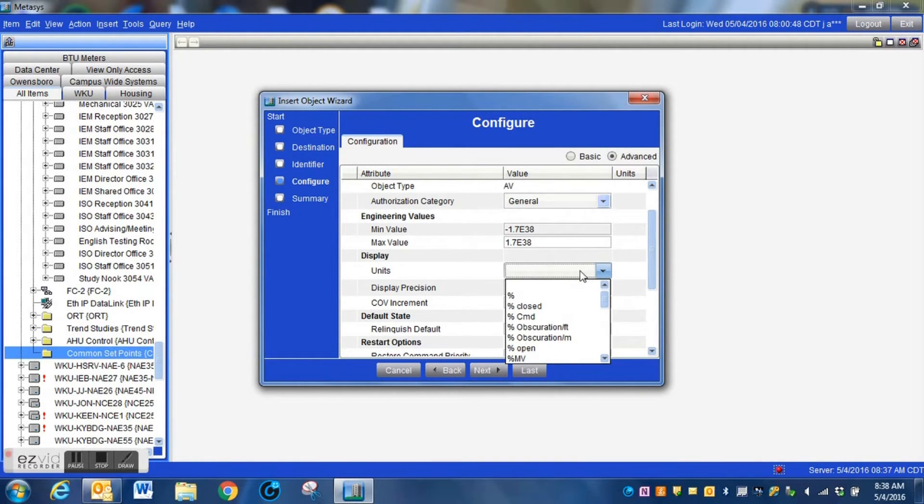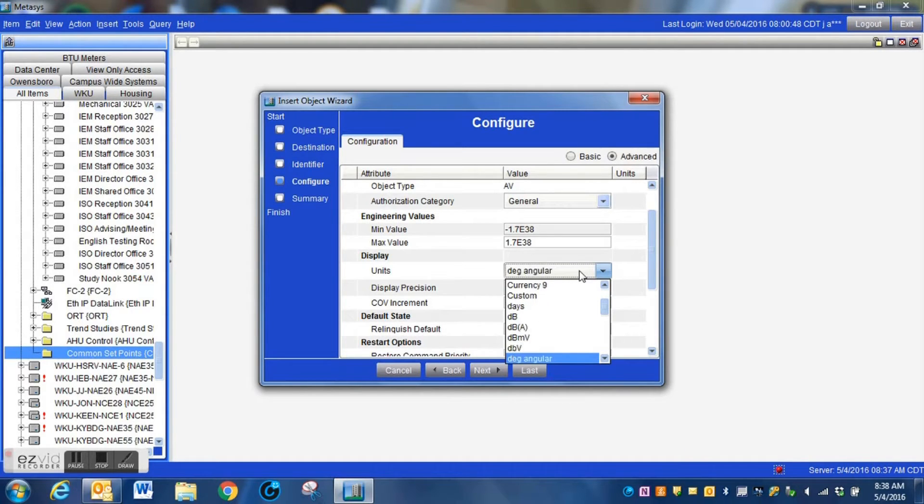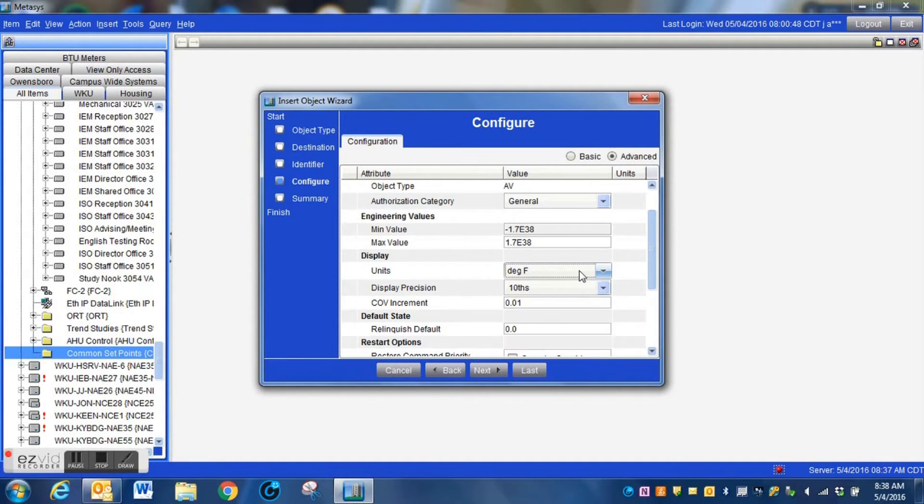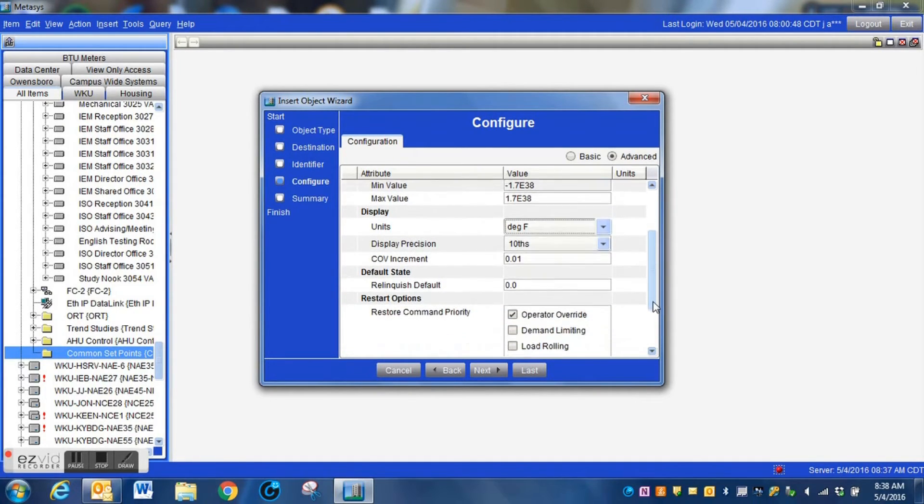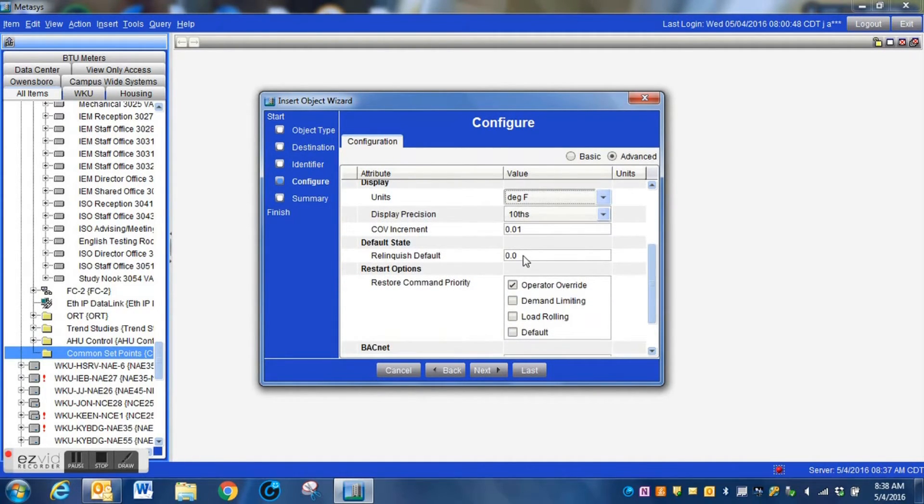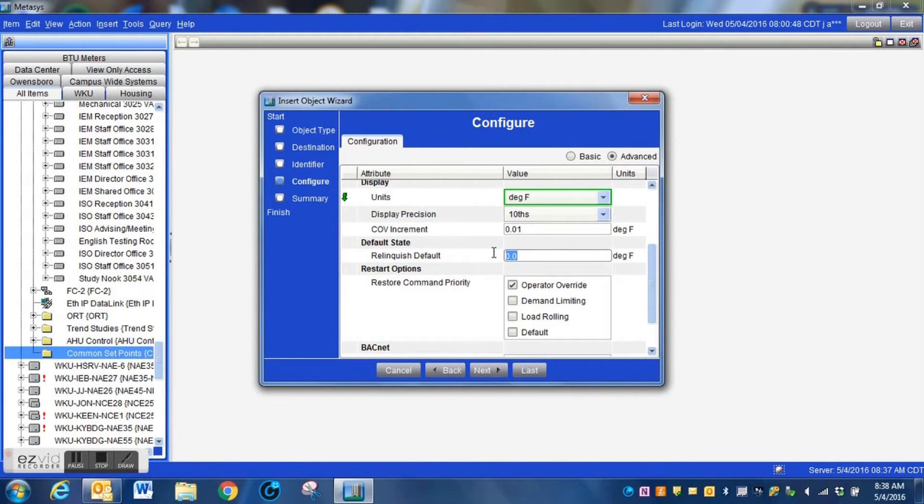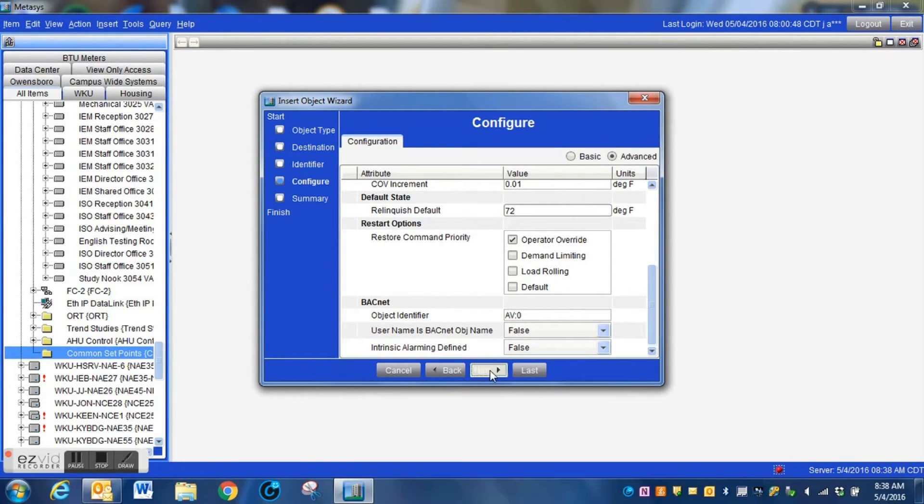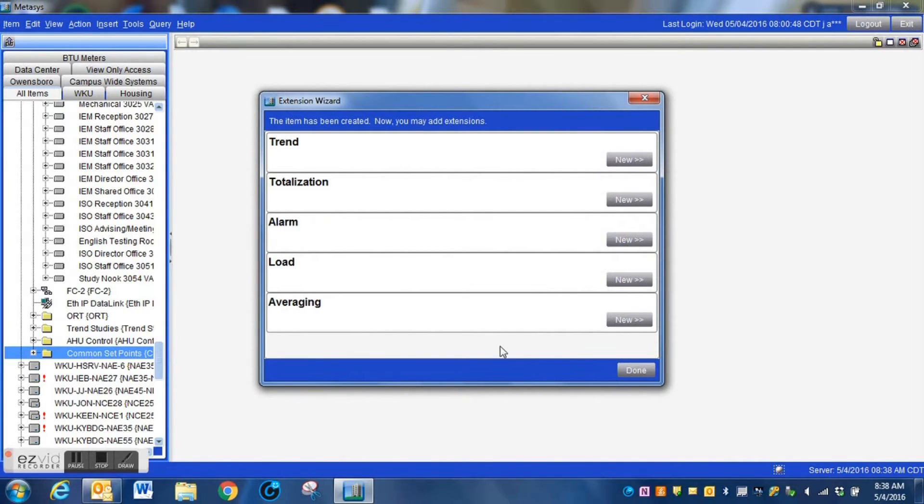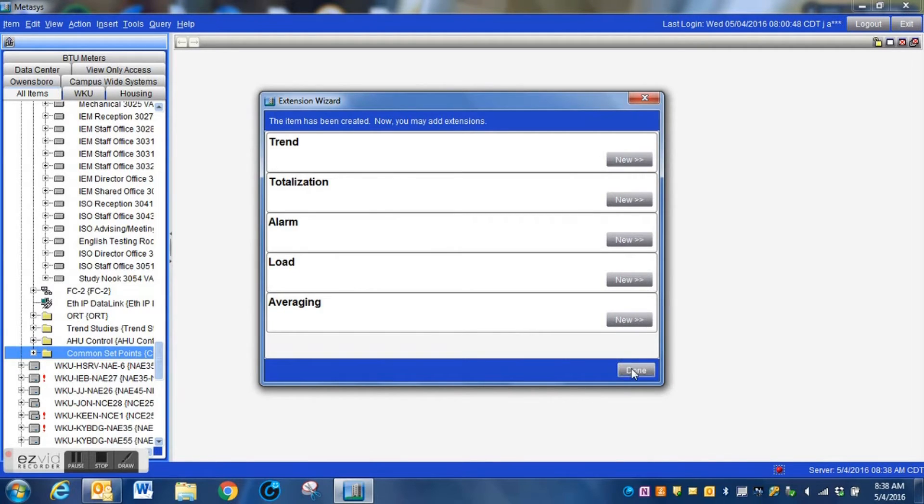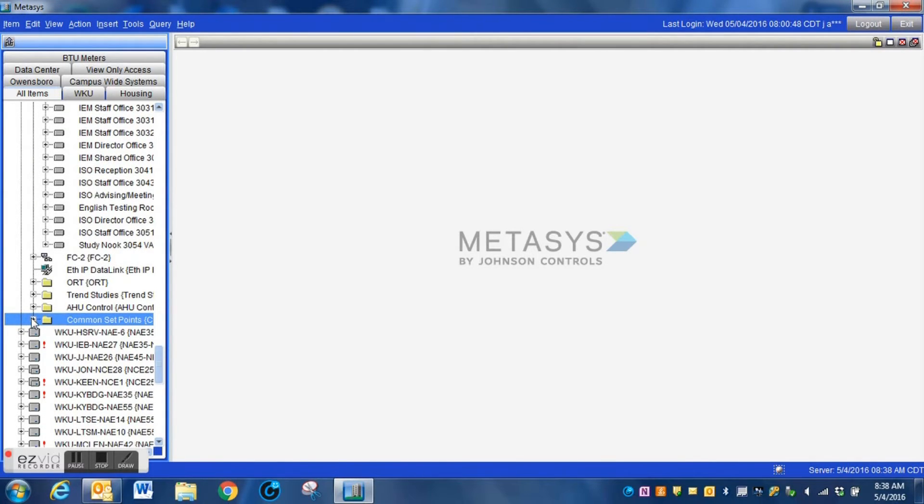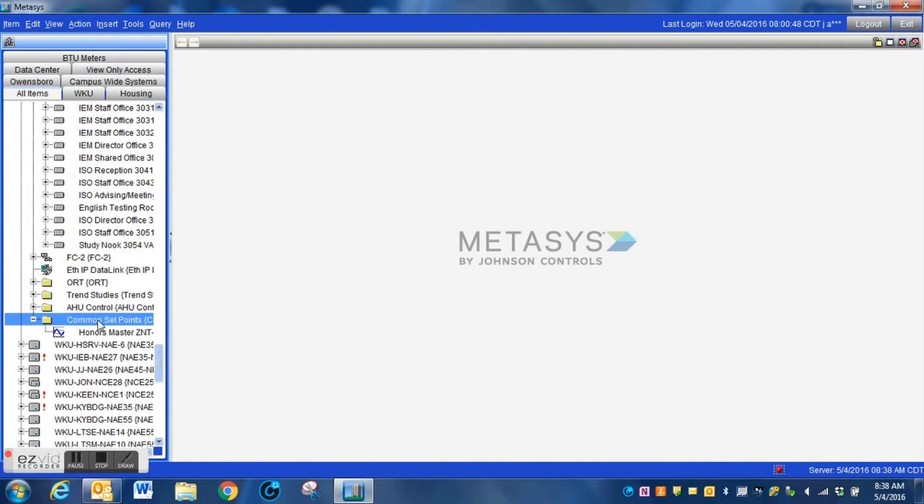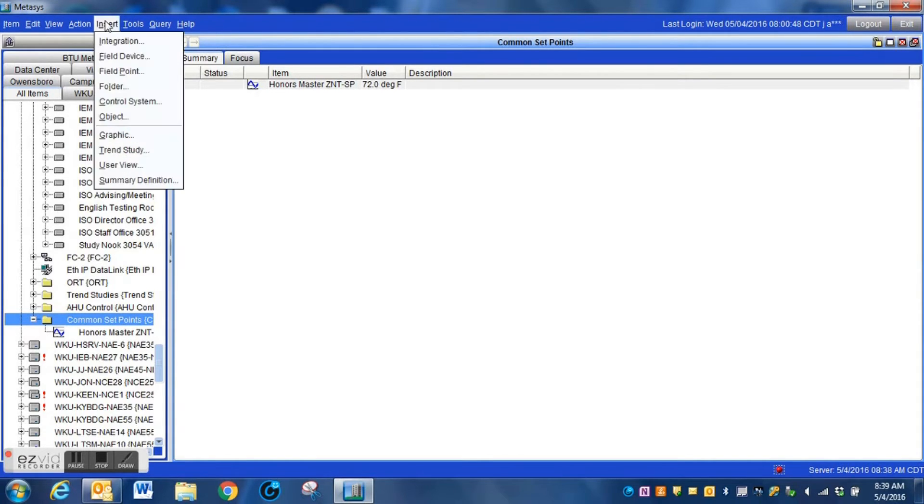Here is the configuration screen. We're going to change our units to degrees Fahrenheit by dropping down this list. Once we have that selected, we are then going to go down to the relinquish default. This is something that I like doing in these. I don't like leaving this at zero. I do like putting in a relinquish default within these analog values when we are dealing with a common zone set point. That way the system, if anything ever happens, it should go back to a manageable point instead of going wild. Once we have that object created, the next step that we are going to do, we can see our object here. This is the point that we just created. You can see it's already put the value at 72 since we put that relinquish default in there.